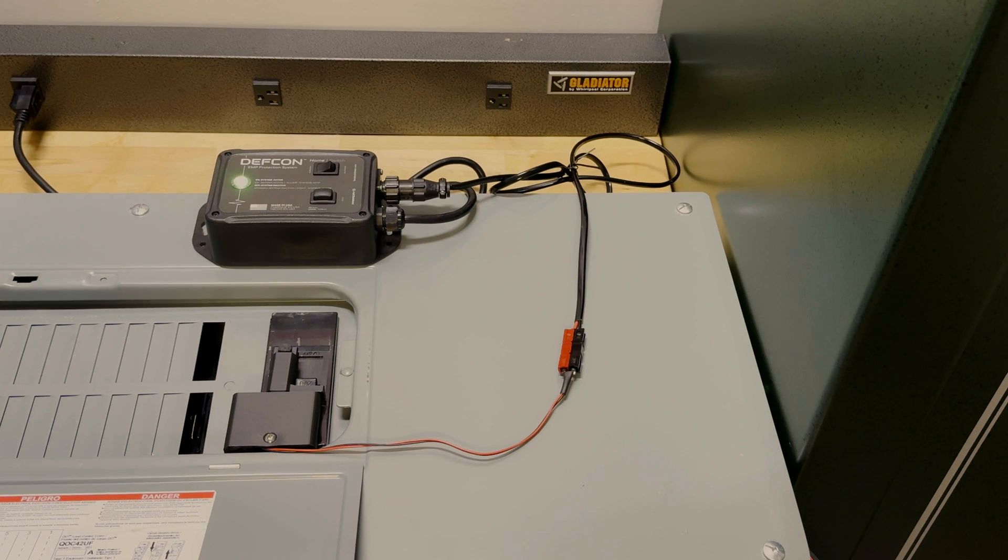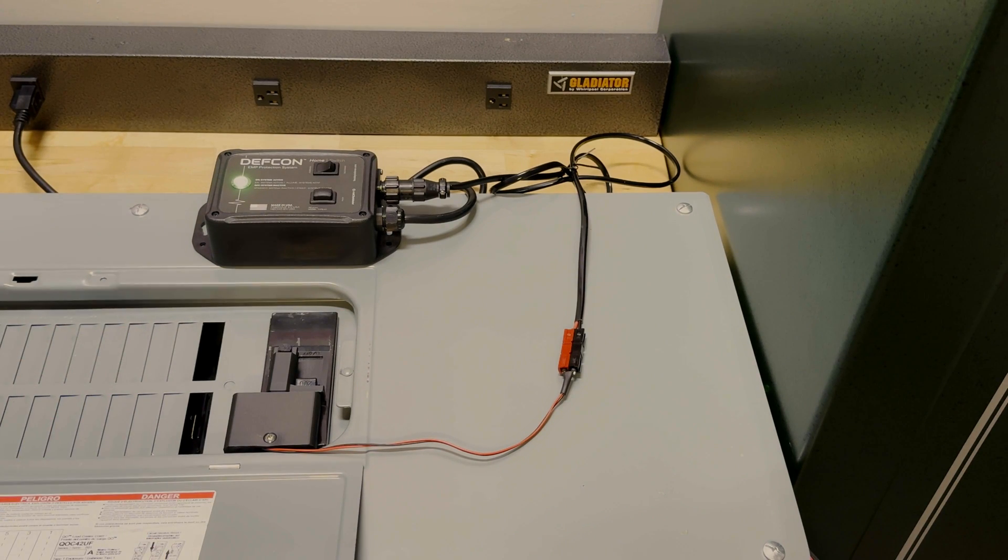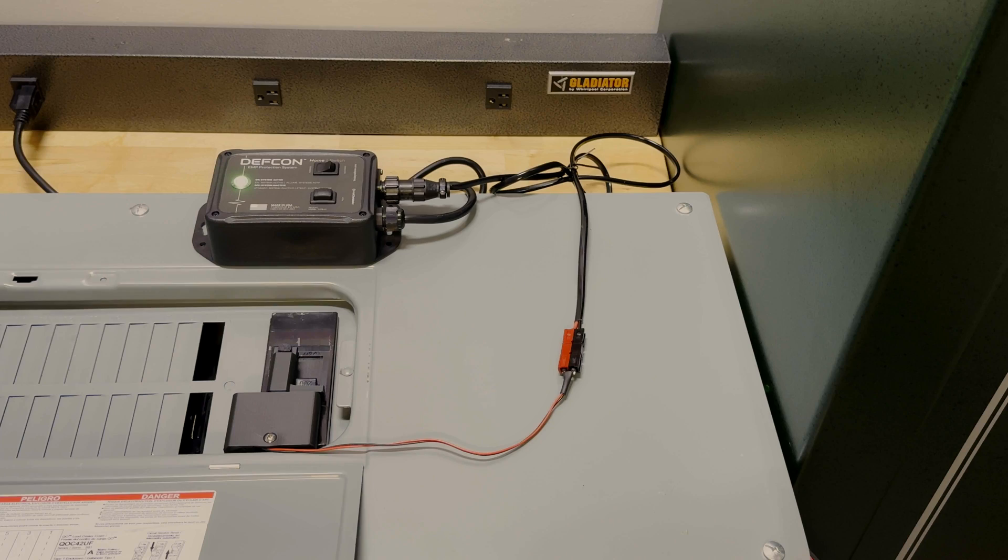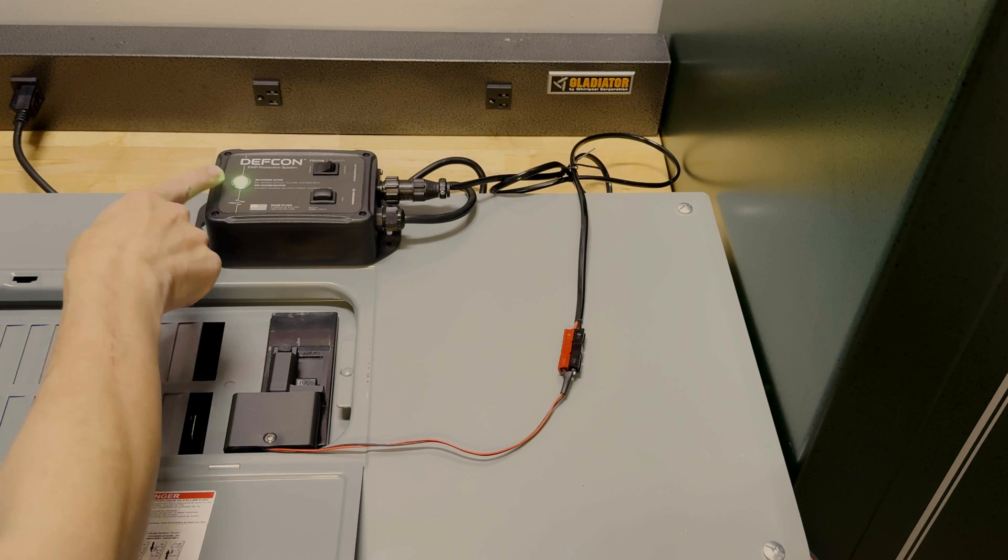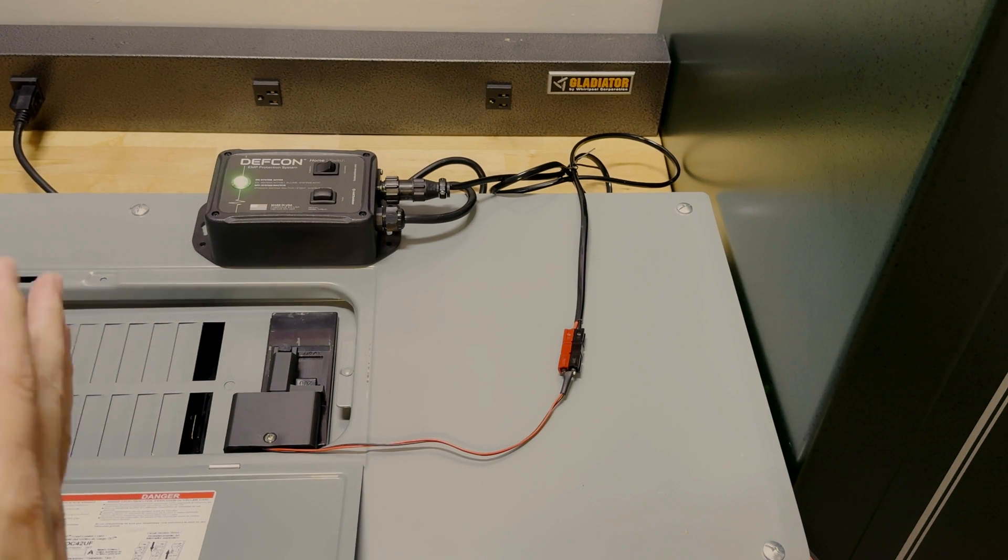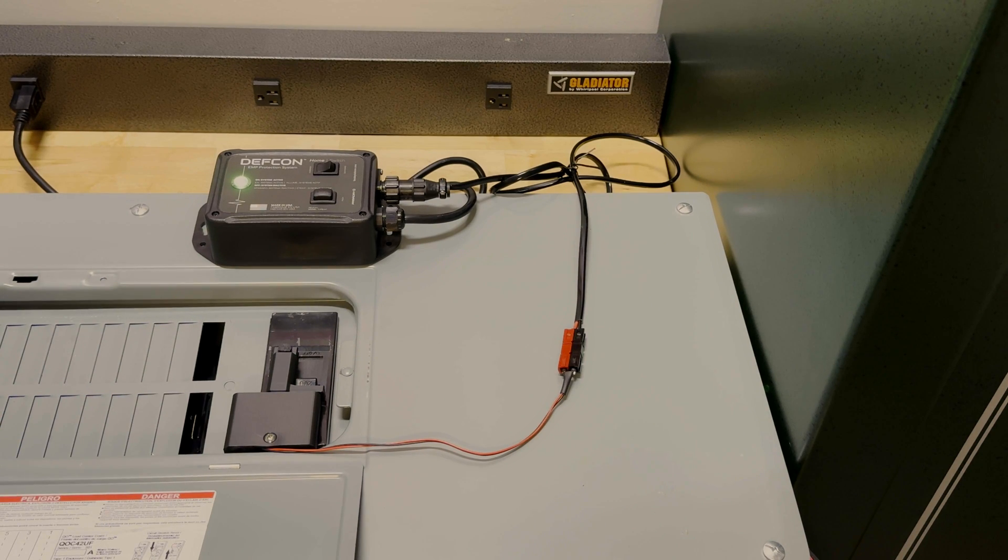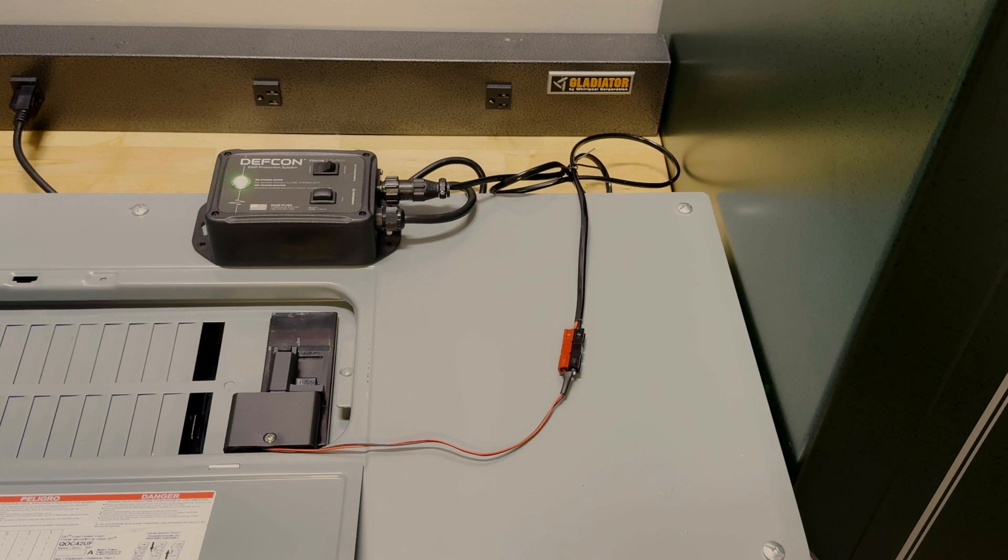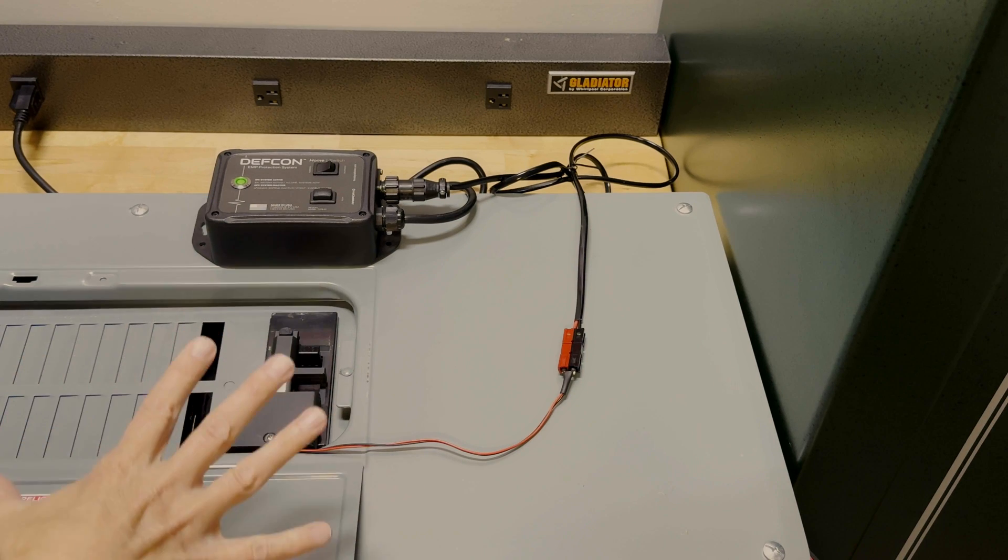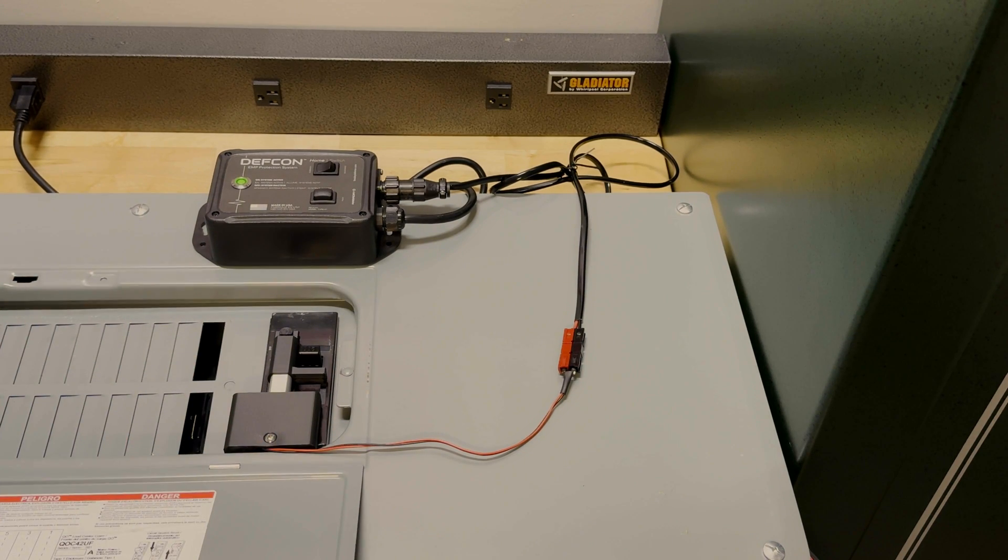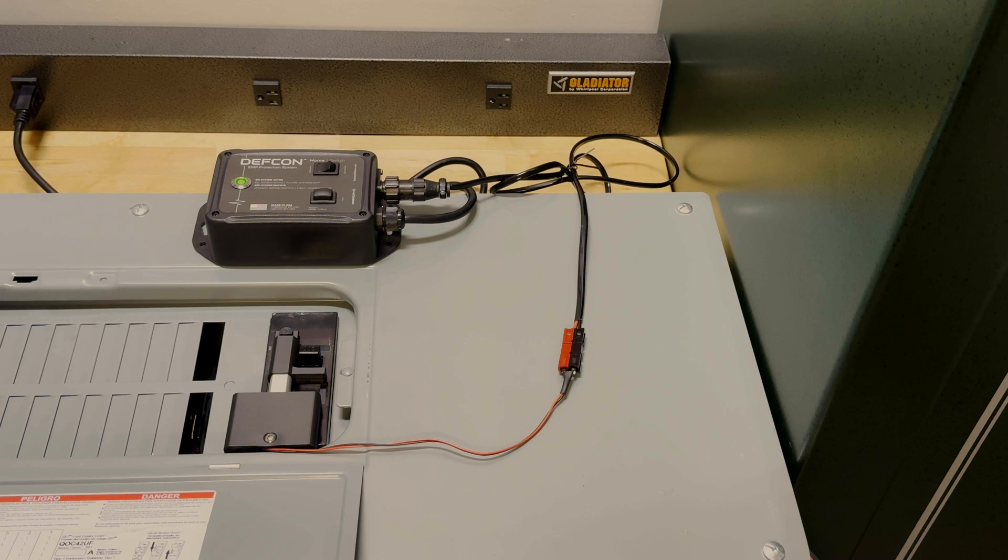Now what you'll see is the actuator assembly will start to move and you'll hear a sound which is just a tone indicating that it is actively driving the actuator. Now once that breaker trips, of course, all power will be lost so this light will go out and the system will be dead. Now we'll have to talk about how to recover from that state after we do this demonstration. Let's fire the pulse. So you see the actuator assembly moving. It trips the breaker. As soon as it trips the breaker, the light goes out and the system is no longer active. So we have now disconnected from the utility grid at that point, saving the home or business from any energy that might be coming in on those power lines.